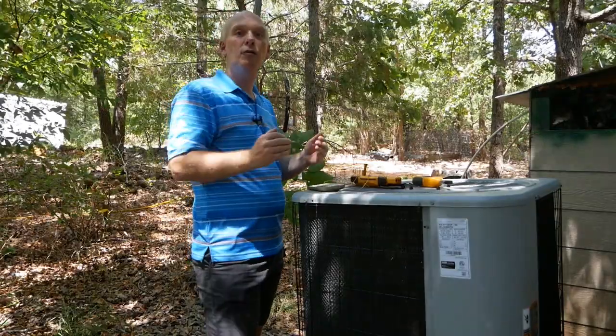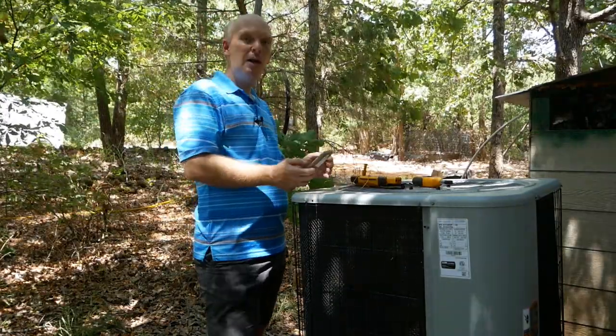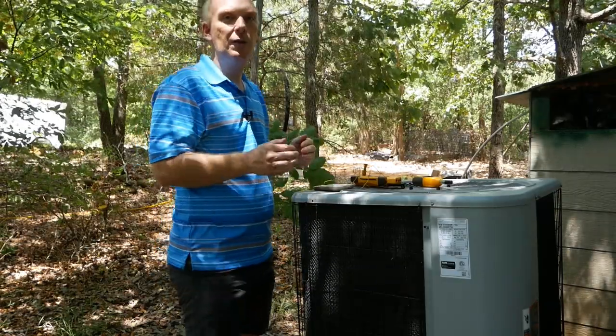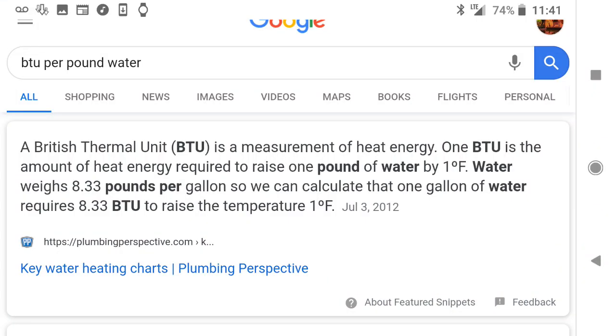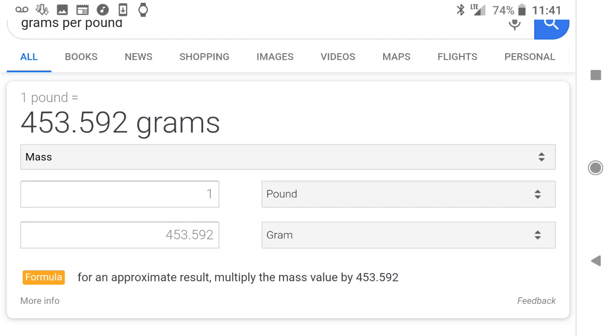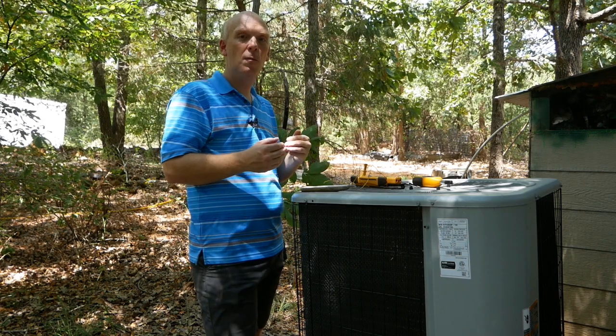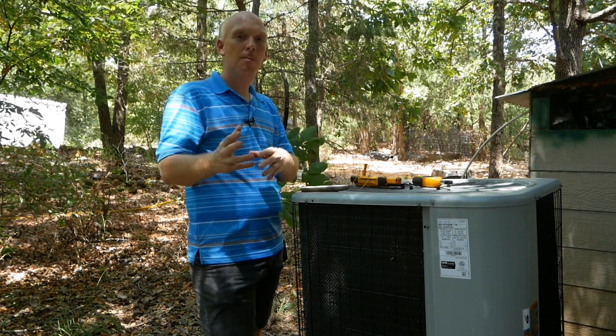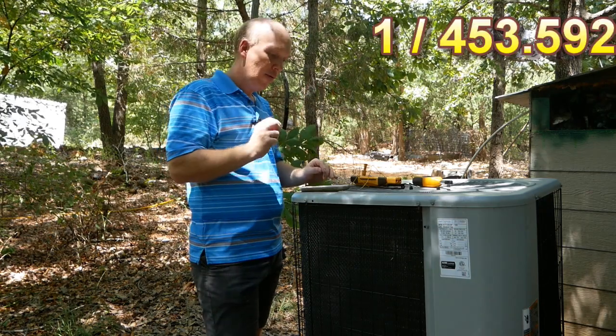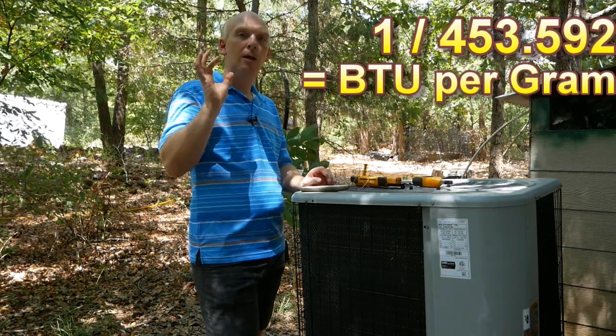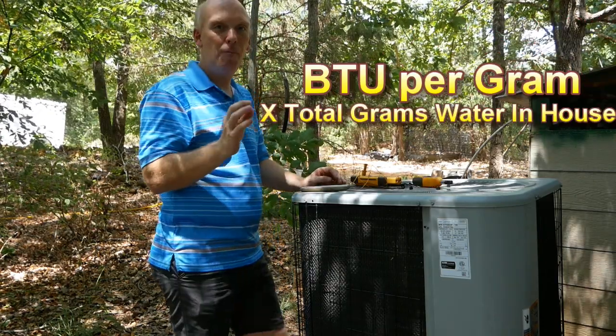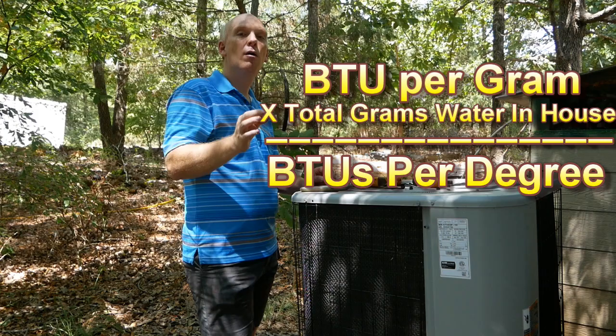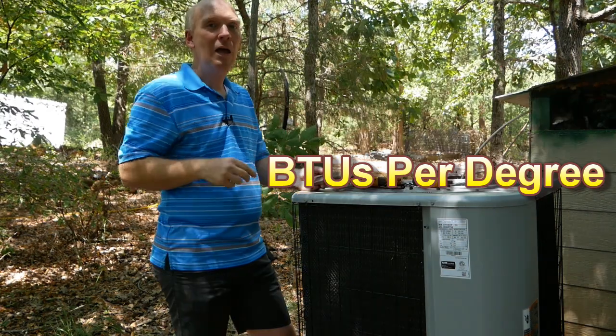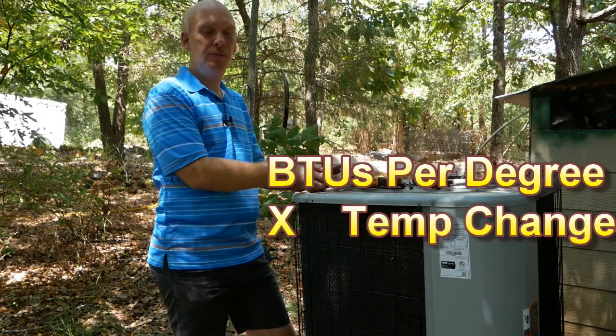But we're not done. We need another data point, so let's look online. We'll find that it takes 1 BTU to change 1 pound of water by 1 degree. Another quick search tells us there's 453.592 grams per pound. So we need the BTU value per gram - divide 1 by 453.592, take this value and multiply it by the total grams of water in the air of your structure, then multiply that by your temperature difference.